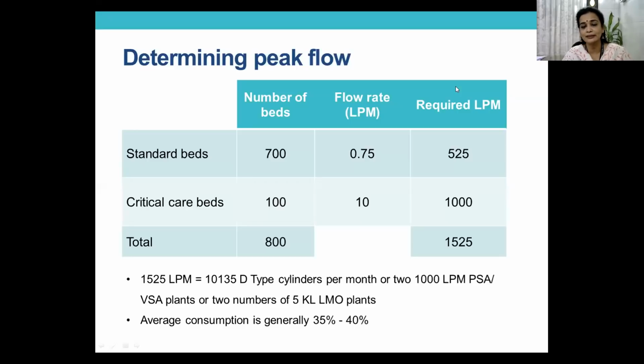For critical care beds, if you have 100, then you calculate for 10 liters per minute. Now your peak load calculation for this 800 bedded hospital is 1525. So in order to cater to this 1525 liters per minute, you need more than 10,135 D-type cylinders, which is humanly not possible. It's a huge supply chain that you're banking on. Or at least 2,000 LPM PSA oxygen concentrators, or 2 numbers of 5 KL liquid medical oxygen plants.